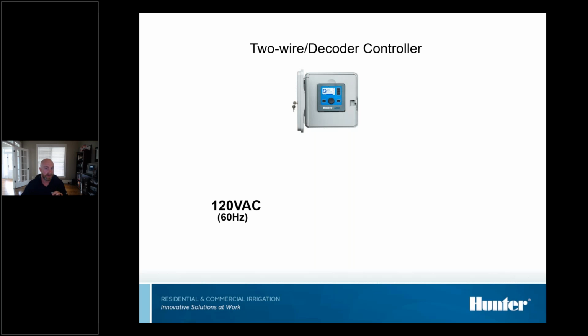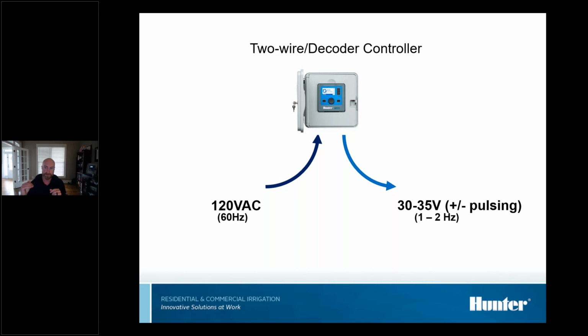This is opposed to a two-wire or decoder controller that takes in 120 volts AC at 60 hertz and puts out a signal that's 30 to 35 volts, and it's pulsing. Pulsing means it goes from positive to negative, and it does that 1 to 2 hertz. We'll talk about what hertz is here in just a couple of slides.